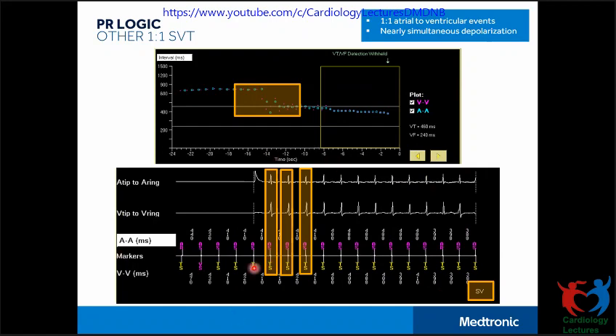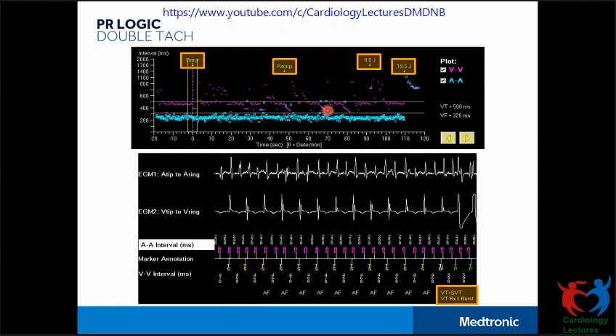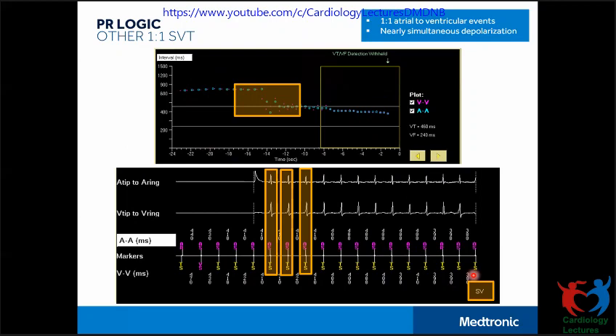The 'Other 1:1 SVT' feature identifies other 1:1 SVTs where atrial and ventricular activation occurs simultaneously, for example junctional rhythms such as AV nodal reentrant tachycardia. In this case, atrial and ventricular depolarization happen almost simultaneously. The device looks at this pattern. In the plot, initially the rhythm was 1:1, but there was an abrupt change in rate — both atrial and ventricular rates abruptly changed going into the VT zone, still following a 1:1 pattern.